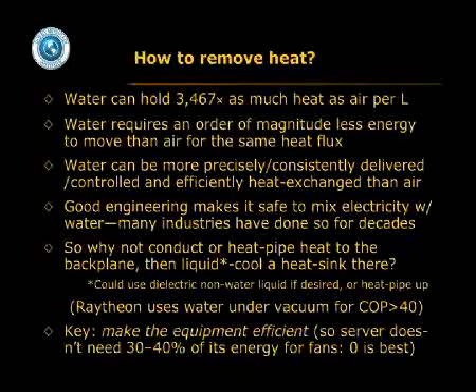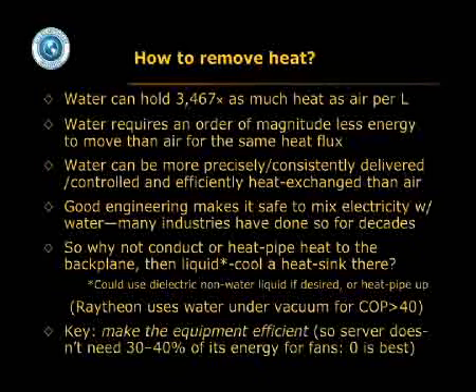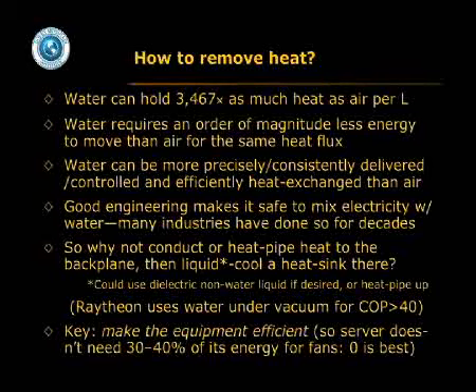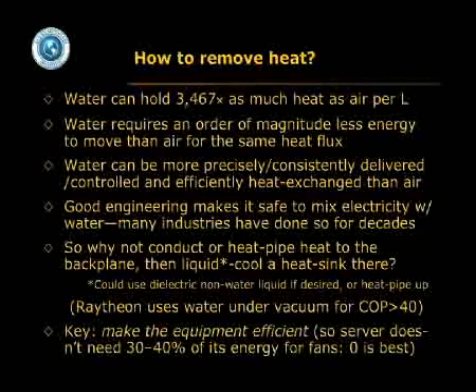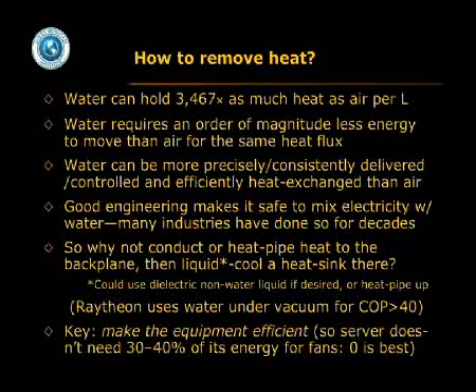So we're starting to see now either direct conduction or heat piping of heat to the backplane, and then liquid cooling from there. In fact, Raytheon has a nice system of subambient cooling. They put water under a vacuum, so they can get COP over 40 on the heat transfer and extremely high power densities. They do this routinely for certain military systems. If you use, by the way, a dielectric liquid that's not water, you could even use a transverse electric field across the heat exchanger to make microturbulence that greatly increases the heat transfer density. Or you could, of course, instead of liquid cooling from the backplane, heat pipe directly up out of the backplane right through the roof to coolers up on the roof, which can be radiant.